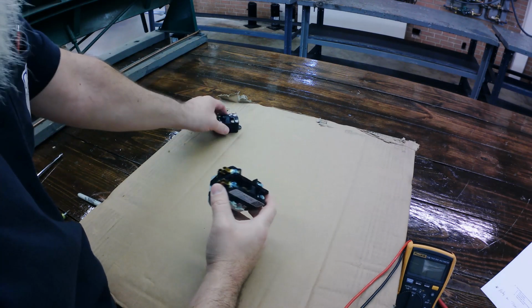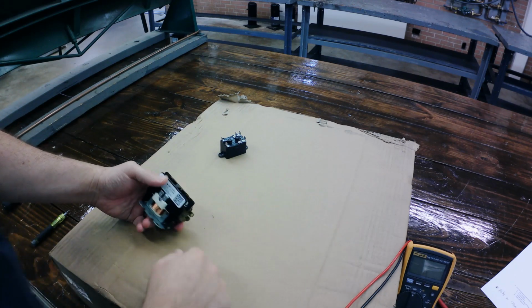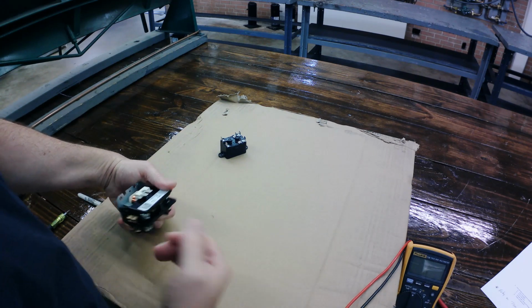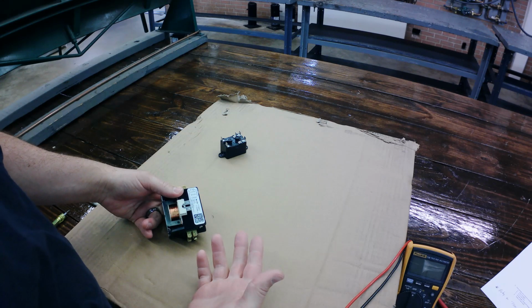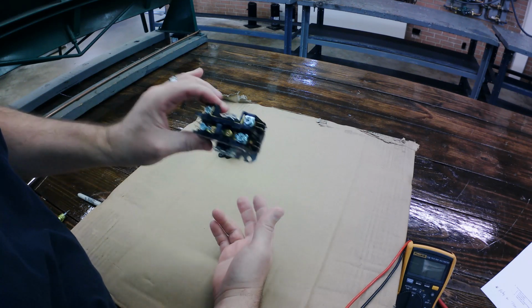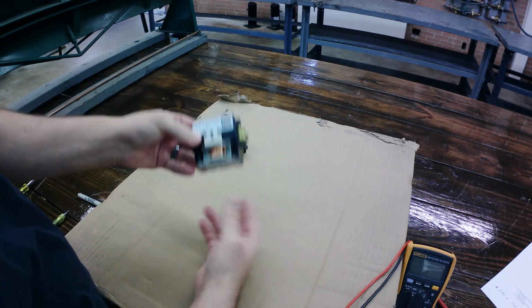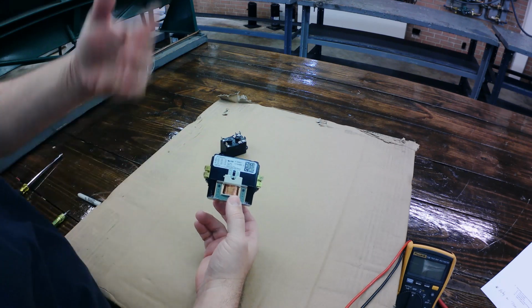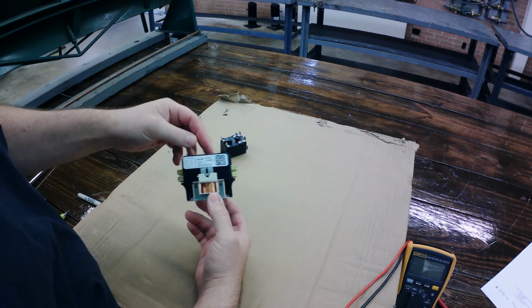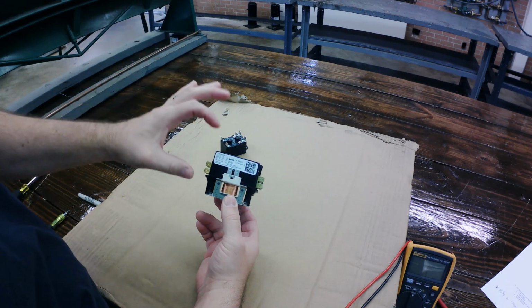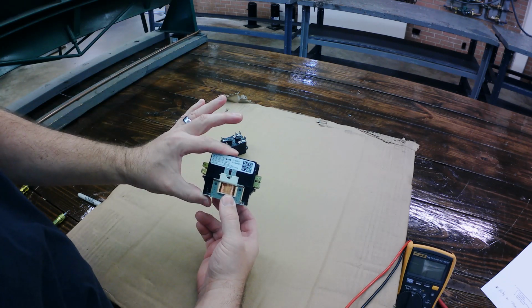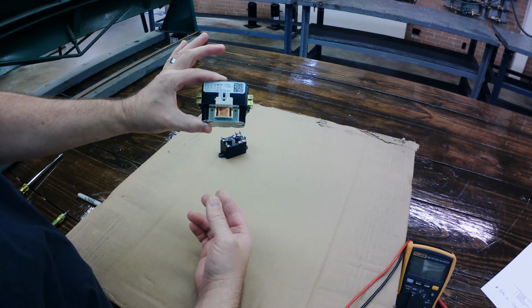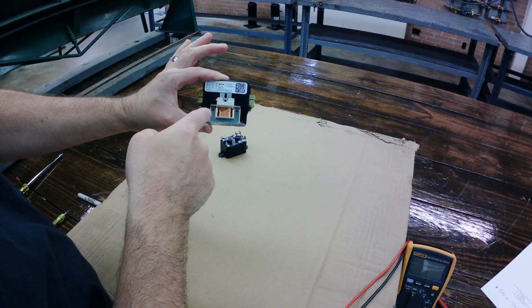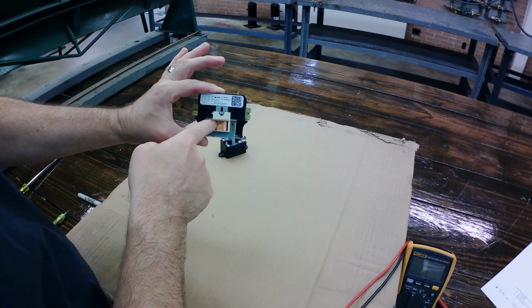All right, so I've got a couple of components here, a relay, a contactor, and a meter, and we're going to start real simple. So what is a contactor and a relay? If you remember what you've learned about contactors and relays, if you've been through any training course or in the field long enough, this is a two-part component. And a contactor is real easy to see. You can identify where the 24-volt coil is.